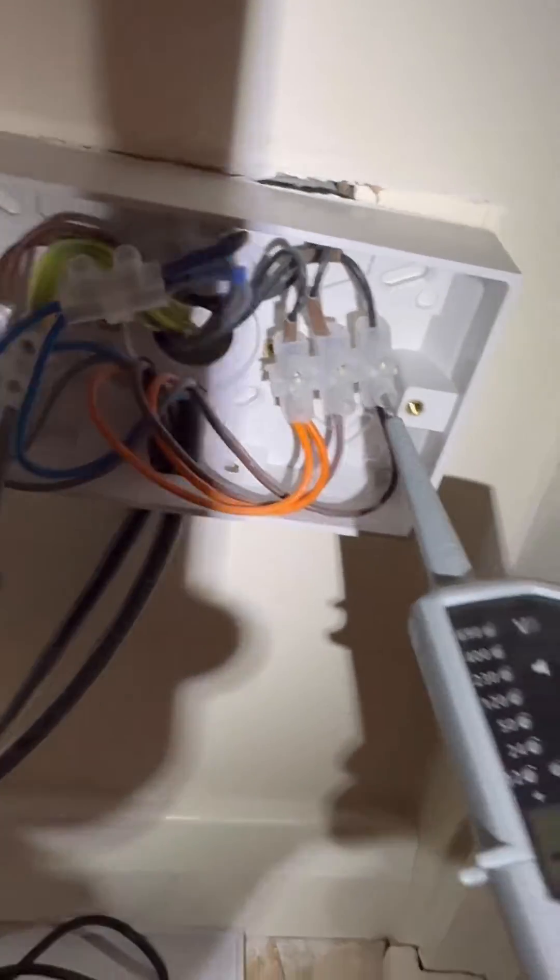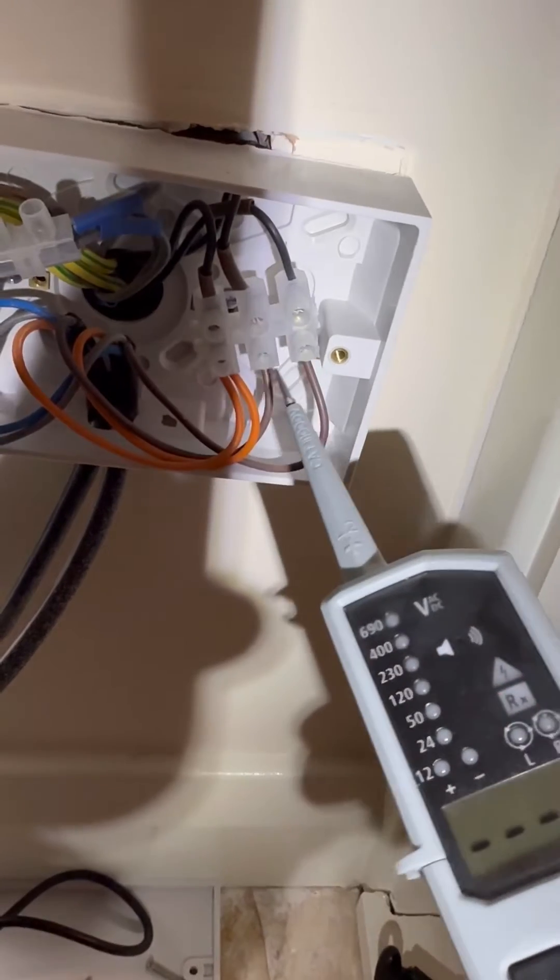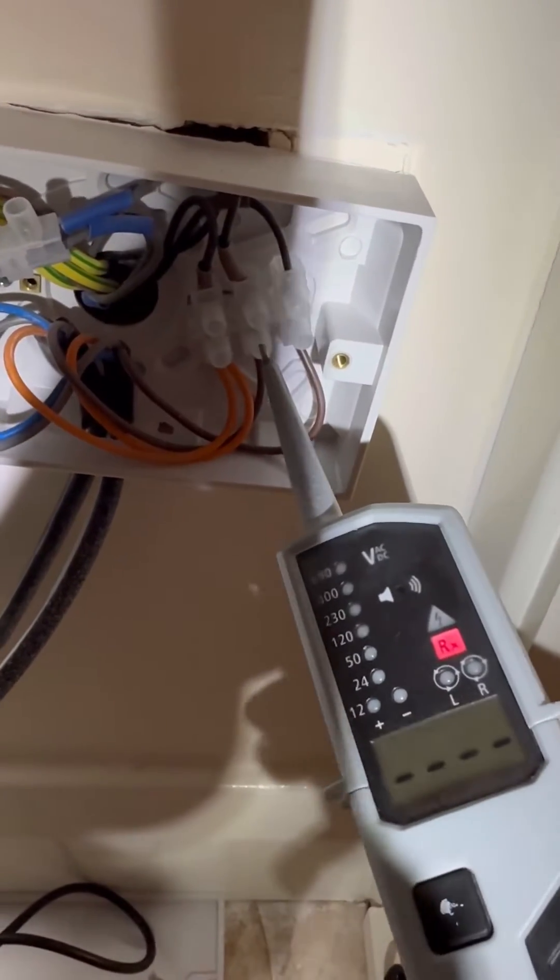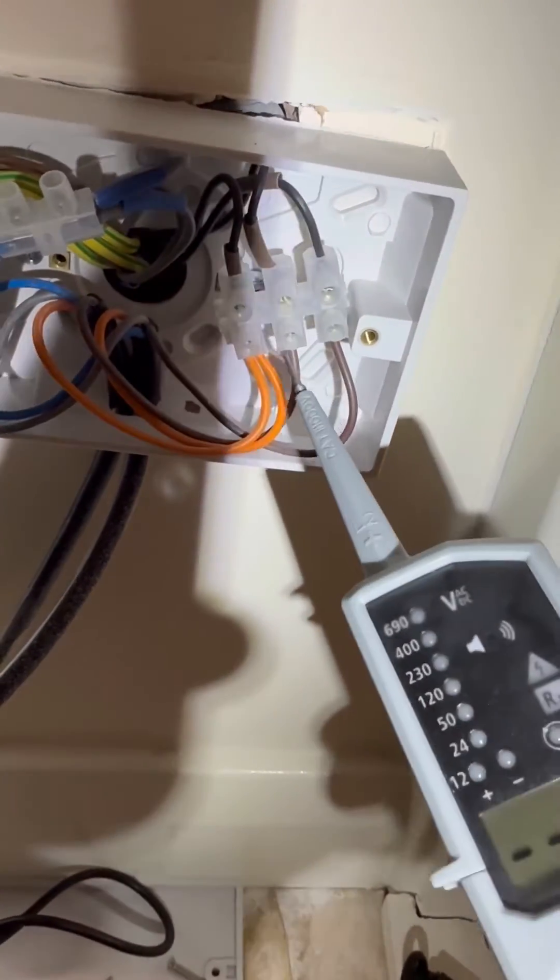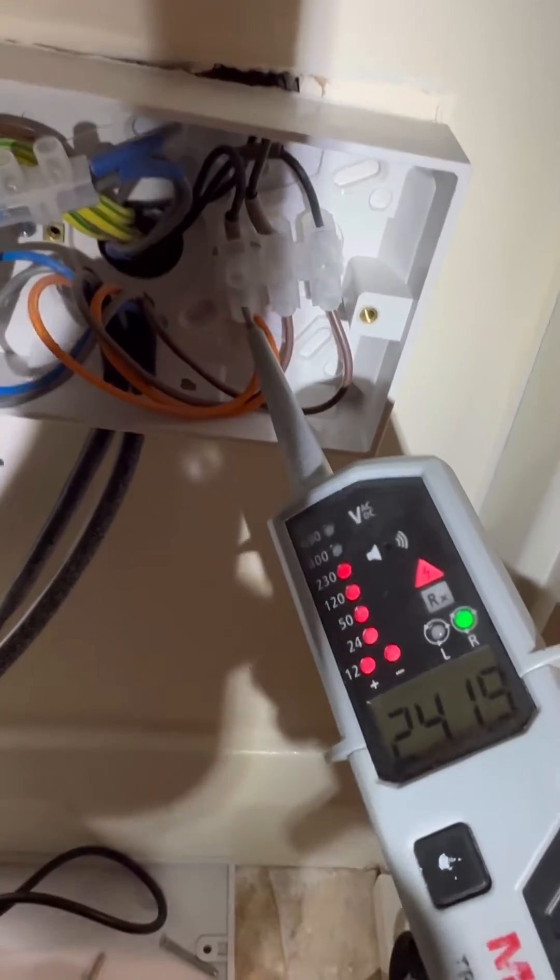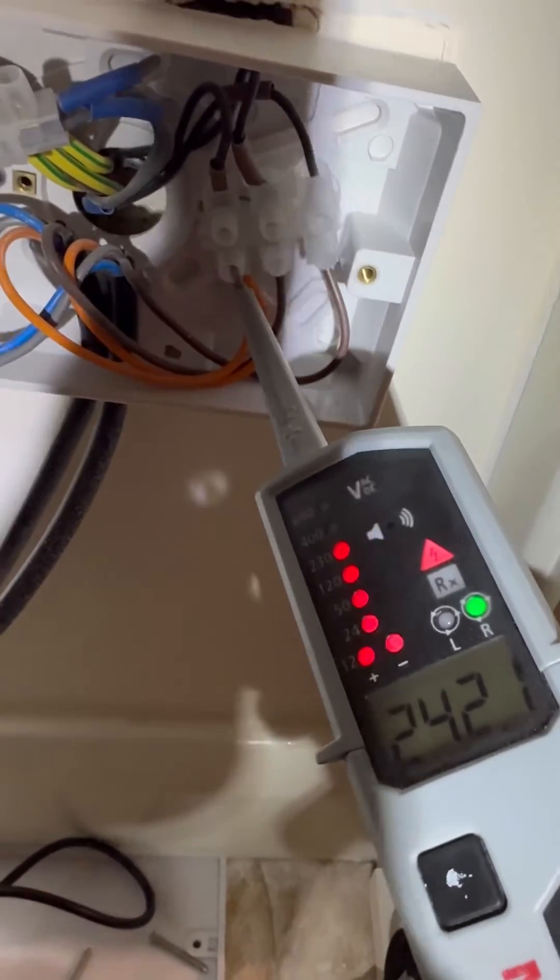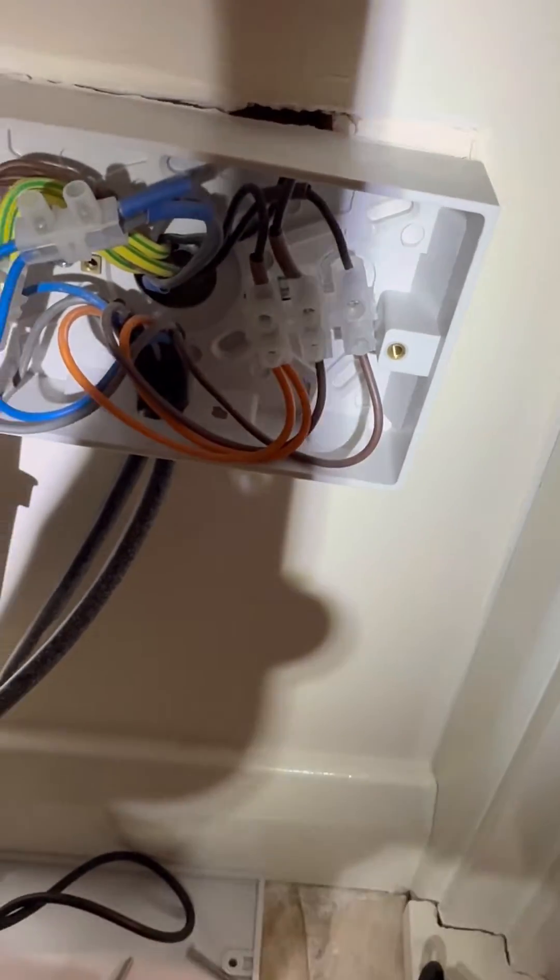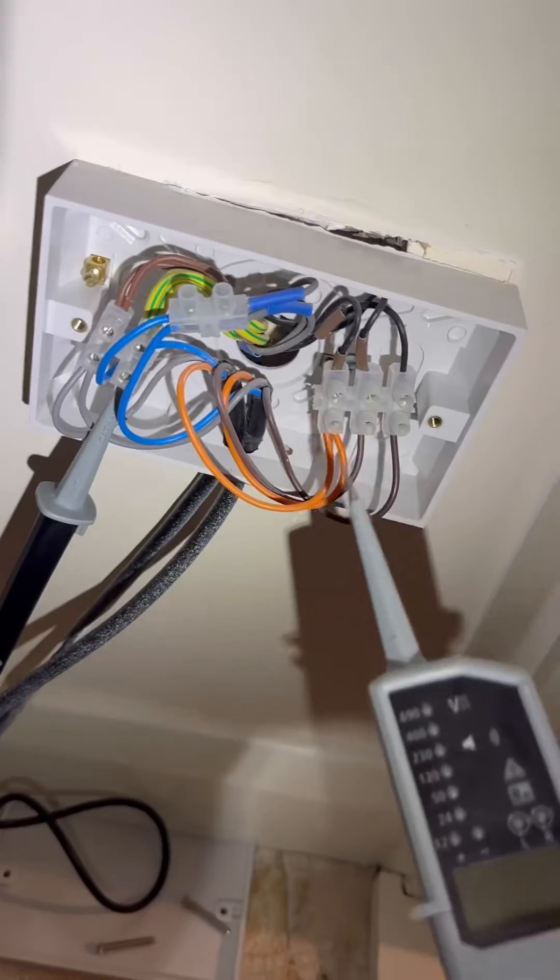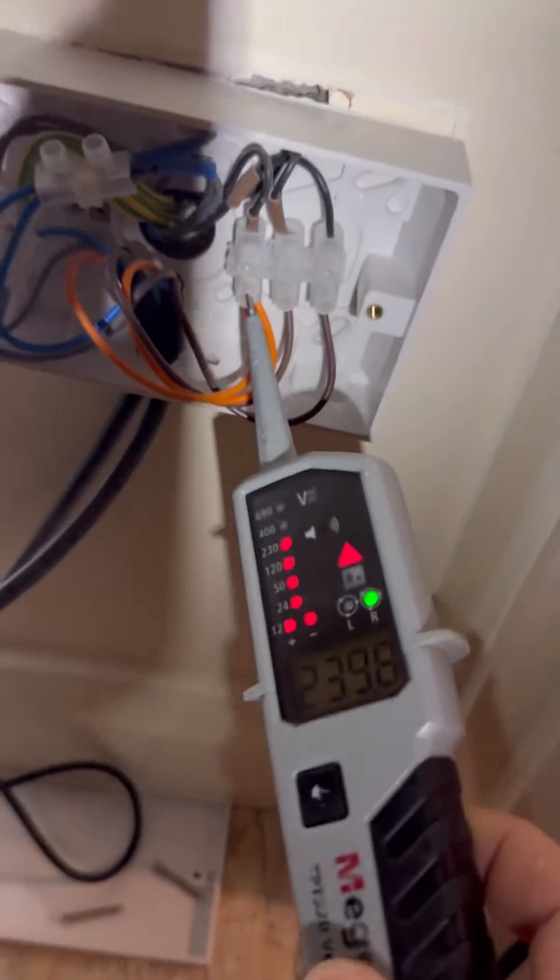Then we're going to check the brown for one of the valves - nothing. Nothing on the other valve. But we're getting 240 on orange, which is a bit backwards because the browns are the call from the stats to the valves. So I wonder where that's actually coming from, having 240 on orange.